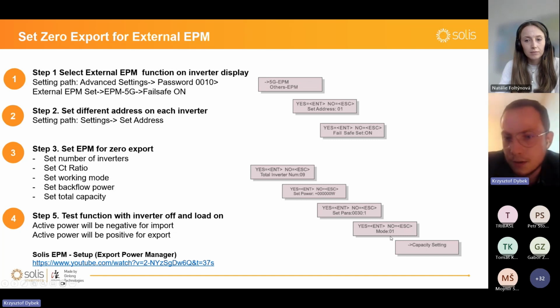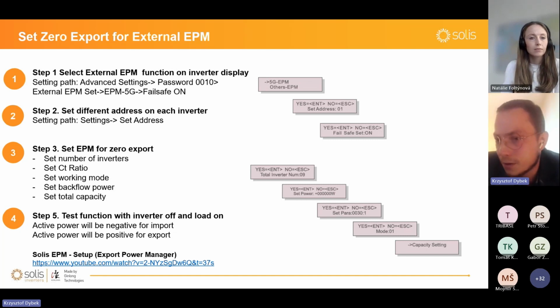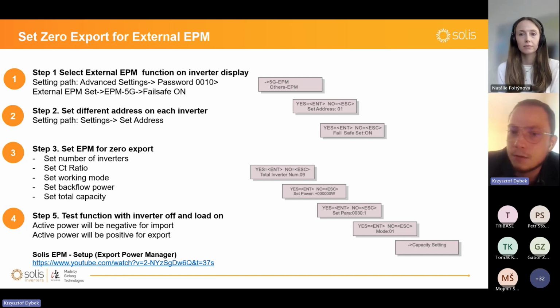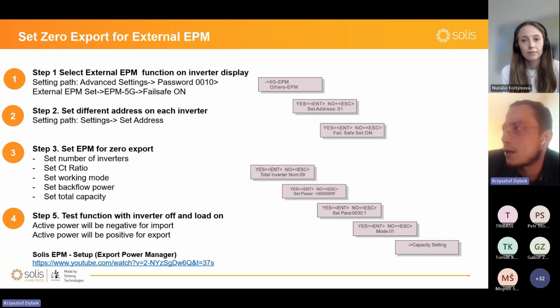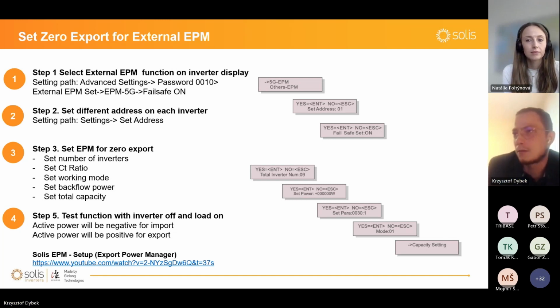Mode 1 is average, means that EPM allows to send something to the grid in case that it will go back, and sum of import-export is still 0. Most grid operators will allow. So the basic is like this. On each phase, inverter will push the same value. Only one line has actual load, so it will go to the grid and then come back to this load. So the sum will be 0.